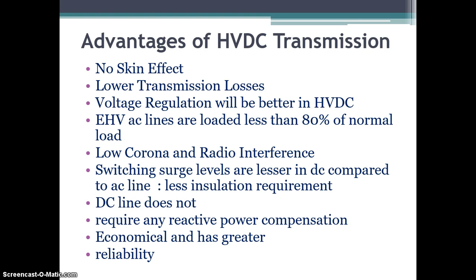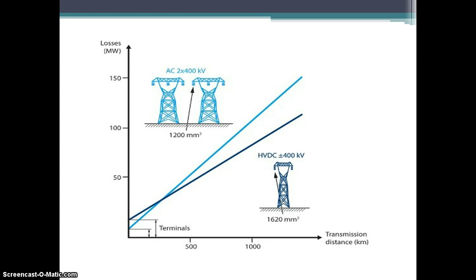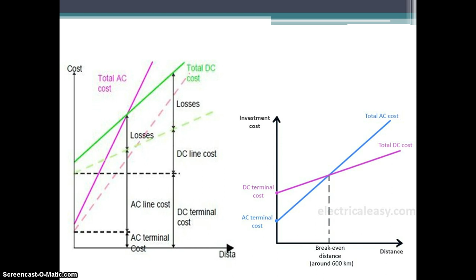Switching surge levels are lesser in DC compared to AC, less insulation requirements. A DC line does not require reactive power compensation. AC has reactive power, but here we don't require any reactive power compensation. The line is economical above 600 km and also reliable. So in the second diagram you can see that the investment cost for an AC line is less up to some point, okay, up to a break-even distance, that is around 600 km, while the DC line initial cost is very high, but after 600 km the total cost of the DC line will go down below the AC line. So an AC line is having a lot of problems, while a DC line with fewer problems and less cost can give you better results. Most of the long distance lines constructed in India are DC lines.